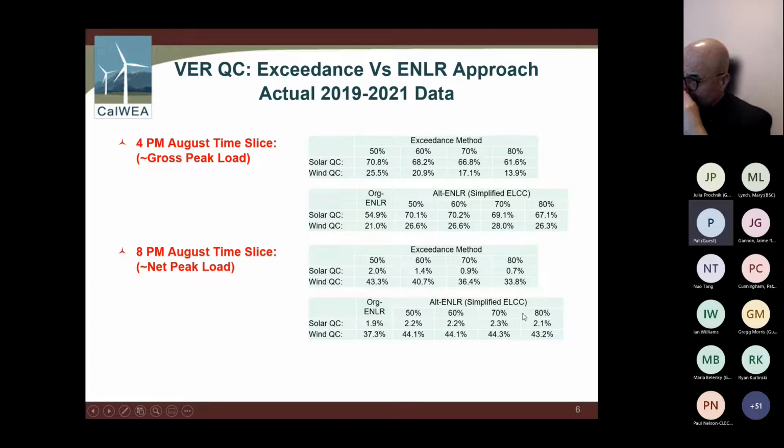But then when we went for targeted sampling, only sampling wind and solar generation when the load was above 50% of the maximum, or 60%, or 70%, or 80% of the maximum, we see the numbers stabilizing, at least when we're using the mean or average number, and also being better representative, especially for wind and solar generation during the times where capacity matters more. In other words, when the load is at 70% or 80% of the maximum or higher.